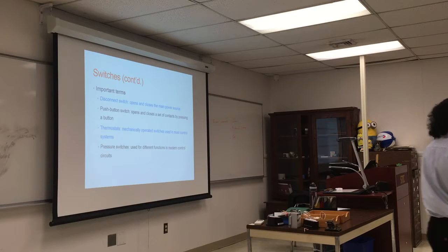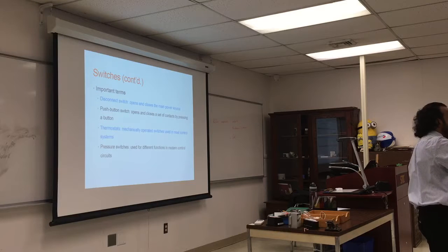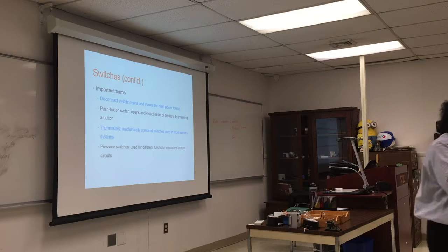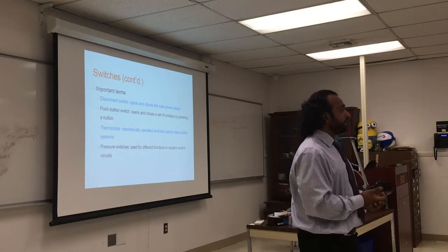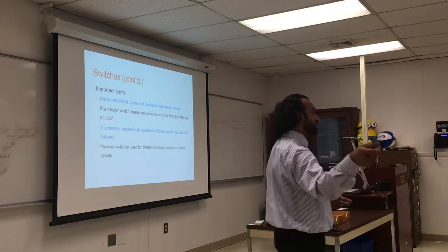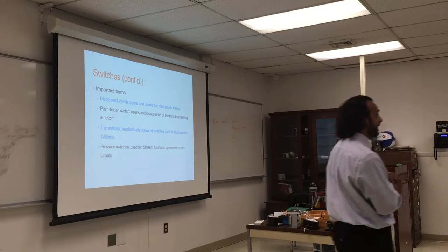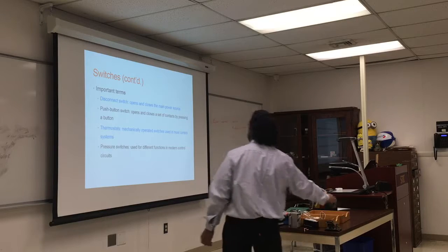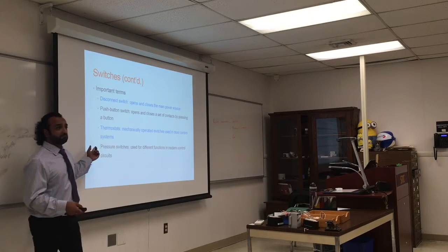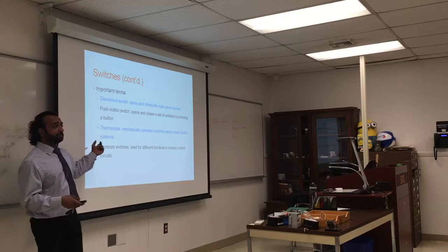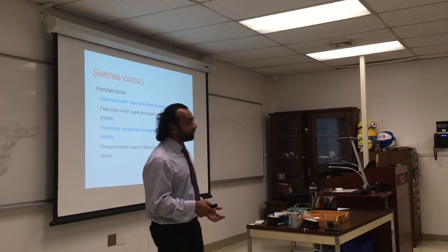We also have a bulb full of mercury, because mercury is conductive. Once it tips, it's going to connect, because we're trying to avoid that little spark. Mercury has been banned in bulbs, because if it bursts, it will produce a lot of vapor. So we have these metallic bimetals, which will snap in action and connect the switch. A thermostat mechanically connects or disconnects voltage. They can be a cooling thermostat or a heating thermostat.